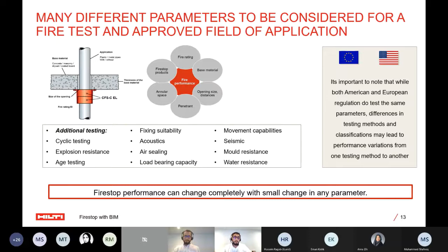Taking it one step further, there could be additional testing required by the designer or client, such as requiring the fire stopping system to have an acoustics rating, or requiring that the system be capable of handling movement. So I want to make sure my fire stop system has that movement capability as well. All these additional attributes can be asked for and provided by any fire stopping supplier if required for your projects.